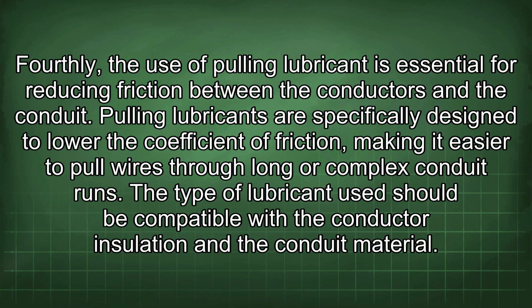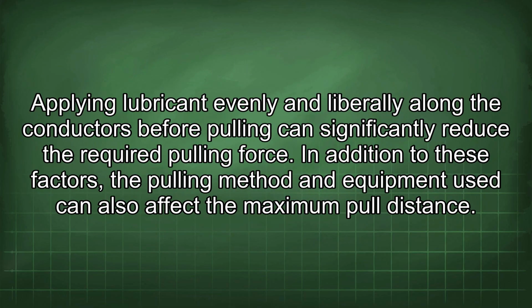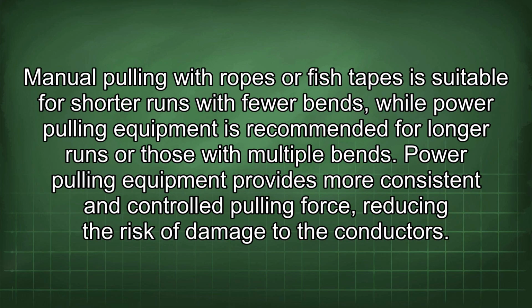Pulling lubricants are specifically designed to lower the coefficient of friction, making it easier to pull wires through long or complex conduit runs. The type of lubricant used should be compatible with the conductor insulation and the conduit material. Applying lubricant evenly and liberally along the conductors before pulling can significantly reduce the required pulling force. In addition to these factors, the pulling method and equipment used can also affect the maximum pull distance. Manual pulling with ropes or fish tapes is suitable for shorter runs with fewer bends, while power pulling equipment is recommended for longer runs or those with multiple bends. Power pulling equipment provides more consistent and controlled pulling force, reducing the risk of damage to the conductors.